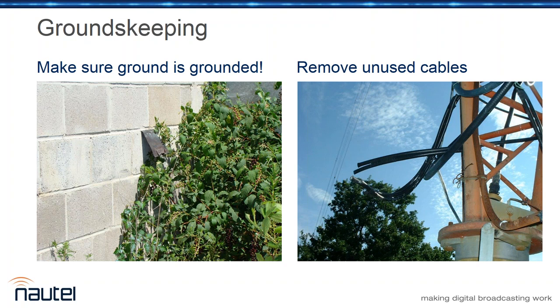We were wondering why they were losing power on modules on a fairly regular basis. Went out to do a site inspection, pushed some of the vines and brush away from the ground egress from the building, and discovered the strap had been cut off, and all the radials and most of the strap were actually gone from the site. So grounds don't do their job if they're physically not there. Seems obvious, but it's the case.